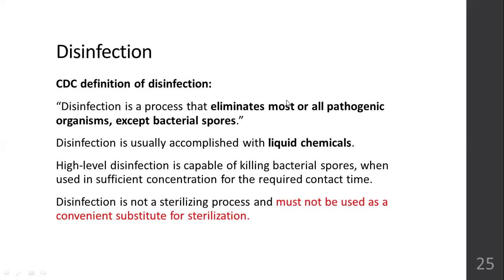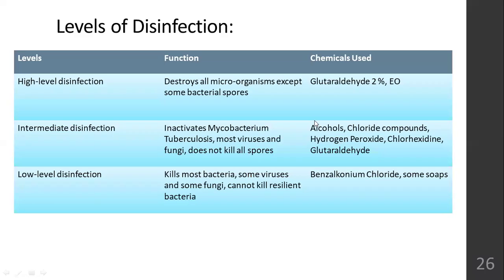And disinfection is not a sterilizing process. High-level disinfection should not be substituted with sterilization. Whichever instrument can be sterilized, it has to be sterilized. Only if the instrument cannot undergo any procedure of sterilization, at that time high-level disinfection is done. So high-level disinfection destroys all microbes except some bacterial spores. Okay, so glutaraldehyde 2% and ethylene oxide come under high-level disinfection.